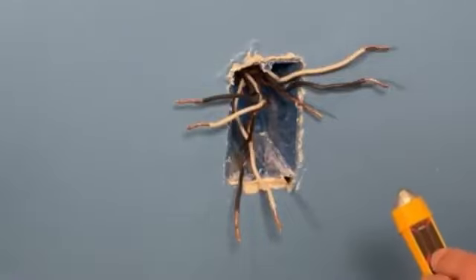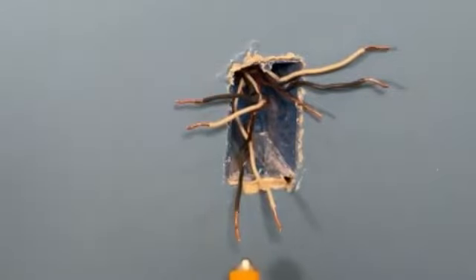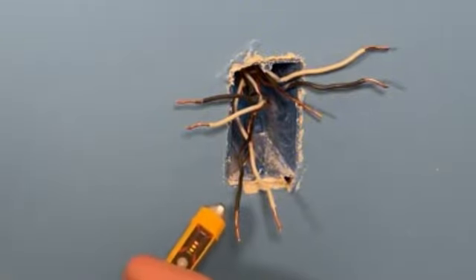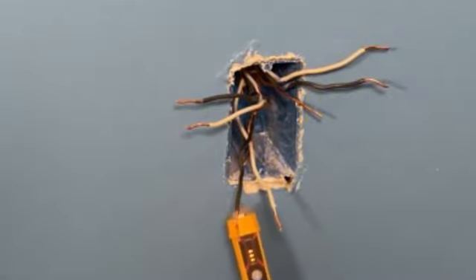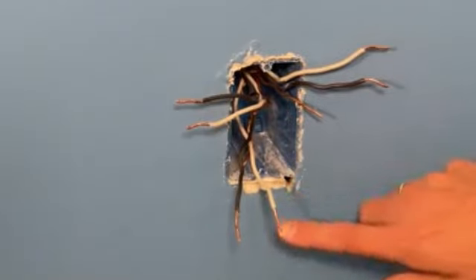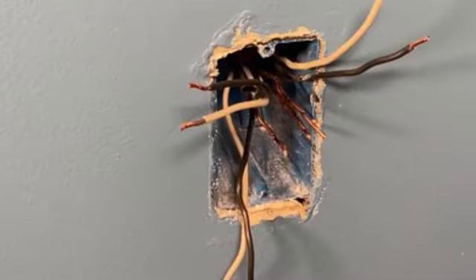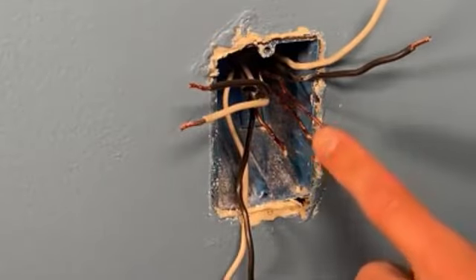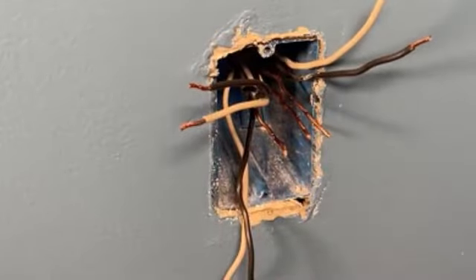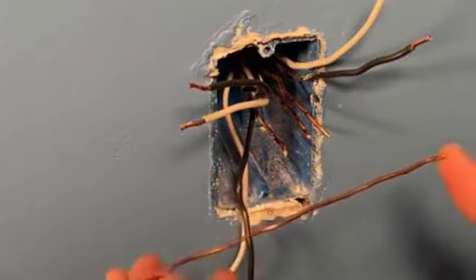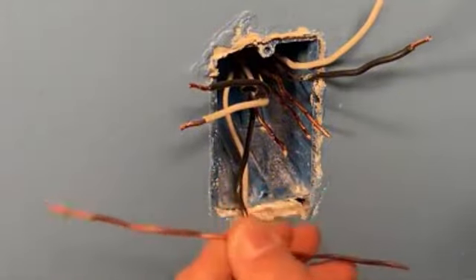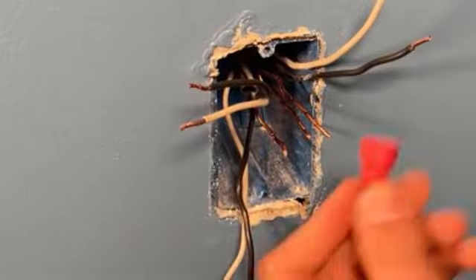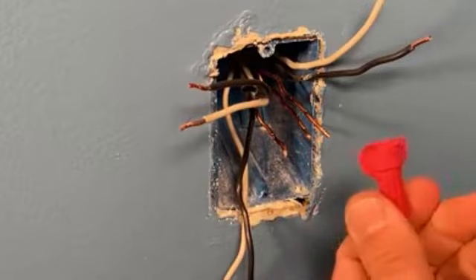Backstab connections rely on a flat steel spring pressing against copper wire. Steel and copper are dissimilar metals. Under pressure and electrical load, they create galvanic corrosion at the contact point. Corrosion increases electrical resistance. Resistance generates heat. Heat accelerates corrosion. This is a thermal runaway cycle. It feeds itself. The connection degrades over 8 to 15 years. That is long enough to survive the builder's 1-year warranty and short enough to fail while you are paying the mortgage.